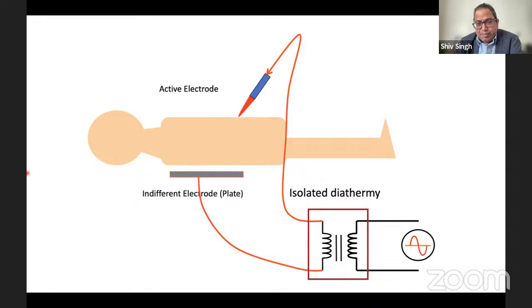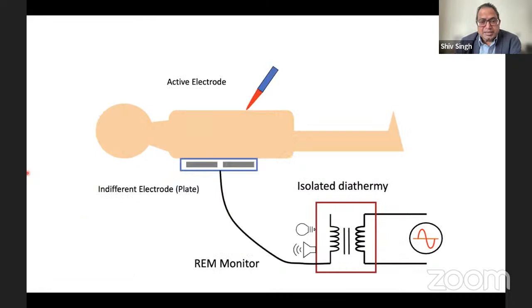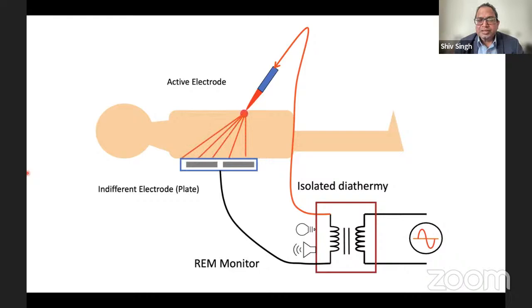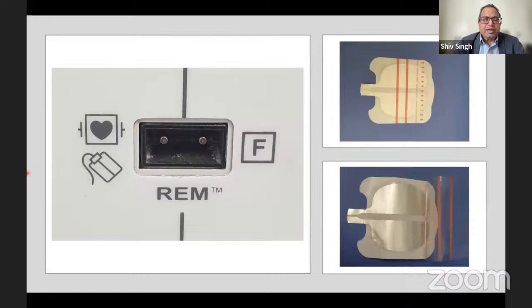This is now the next generation of the same thing. It is called REM monitoring. These new plates had a two electrode system. The active electrode was the same, but the indifferent electrode had two plates. If for whatever reason there was any disconnection at any point, it would detect it and give you an audio and visual alarm. This is the return electrode monitor. This is a new diathermy machine, and if you look at it closely, there are two points in the REM system.